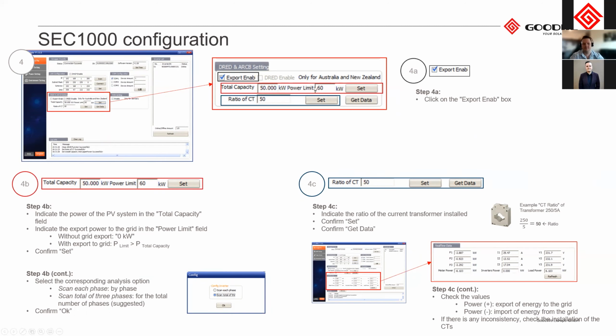Then we have our power limit. So this is, are we allowed to export to the grid? If you're allowed to fully export to the grid, you can put your total plant capacity there. You can even use your PV capacity there as a limit. But if you're not allowed to export to the grid, you just press 0. Once you press set here, it will give you two options. As you can see at the bottom left of the screen, it says select the corresponding option. So you're going to get scan each phase or scan total of 3 phases.